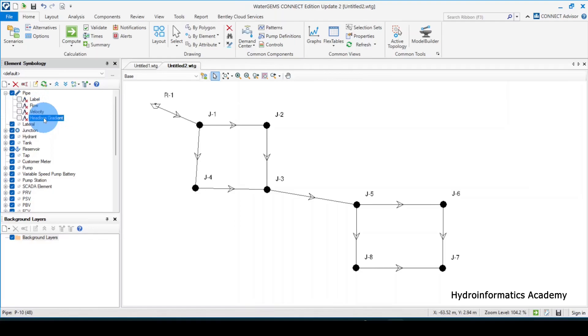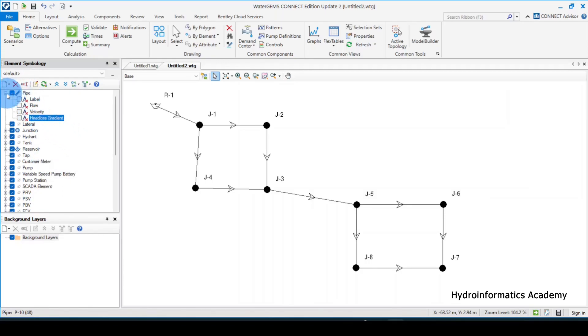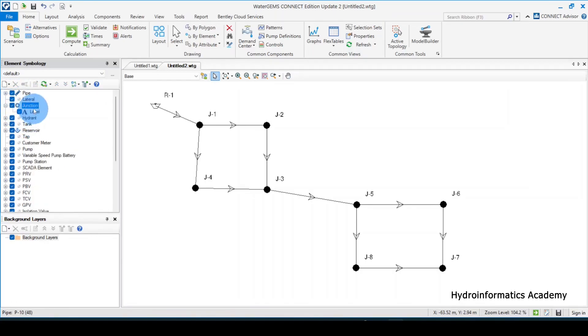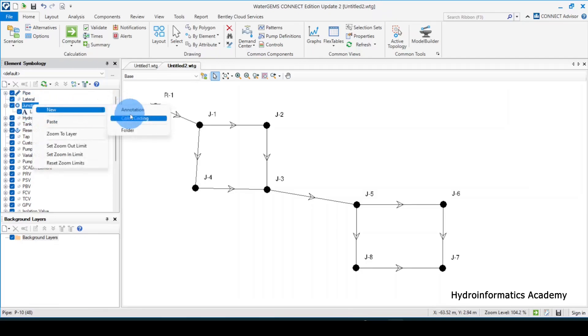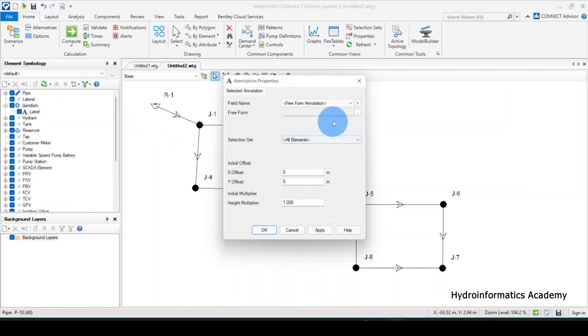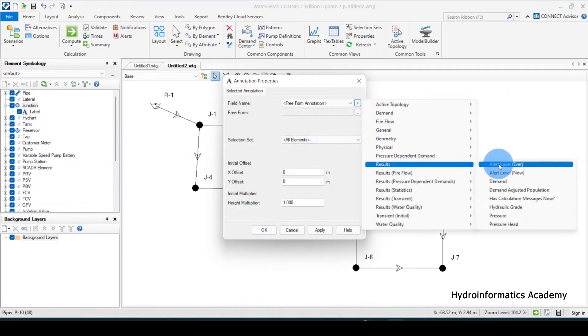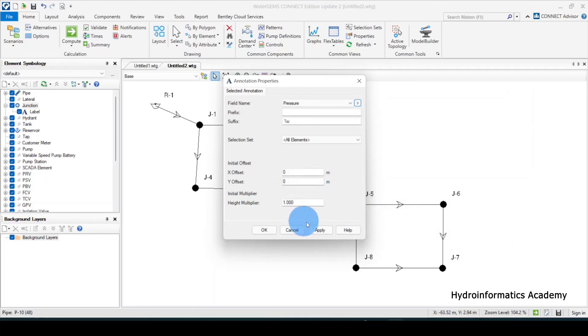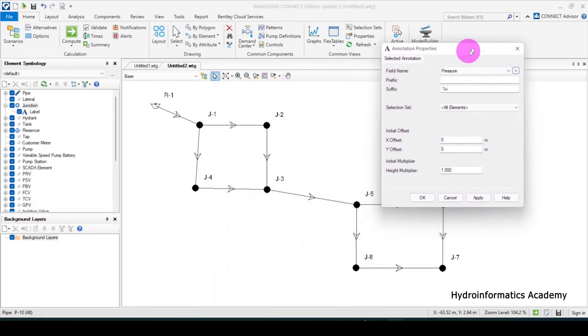The next parameter to take into account is pressure — residual pressure. We cannot view pressure on the pipes directly. Pressure can only be viewed using the junctions. From the junction annotation settings, I'll select results and then select pressure. As soon as I click apply, the pressure results appear.